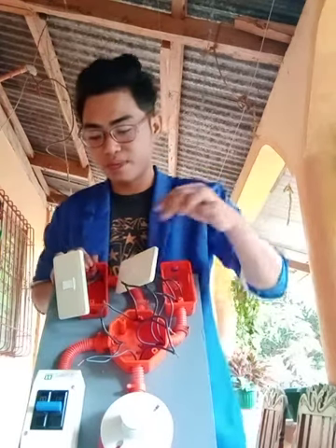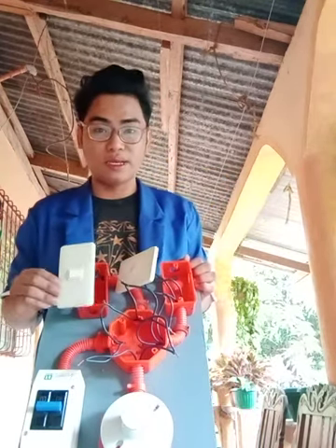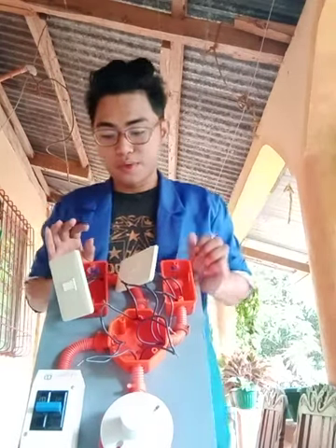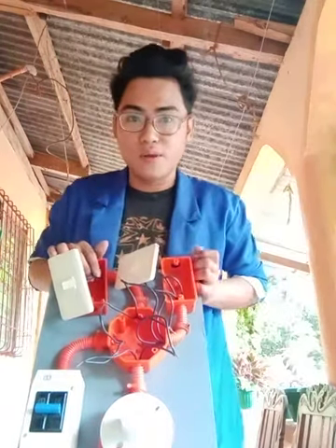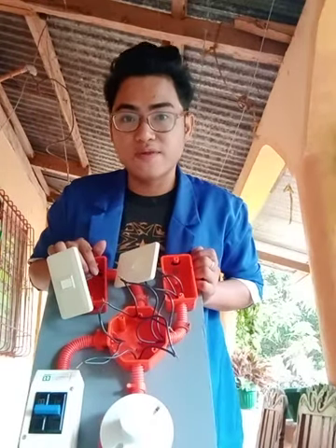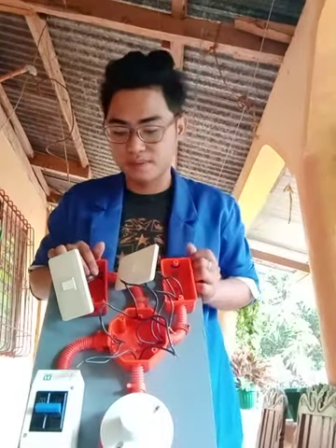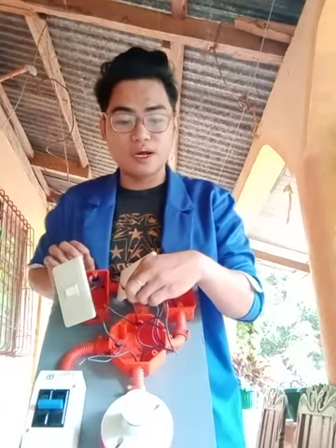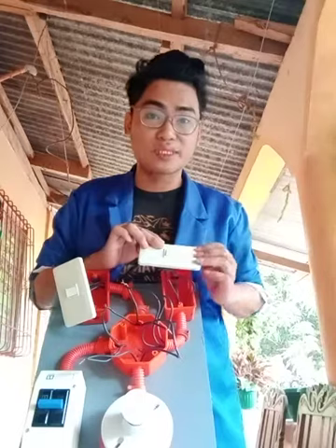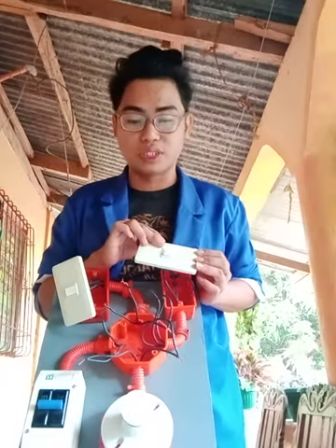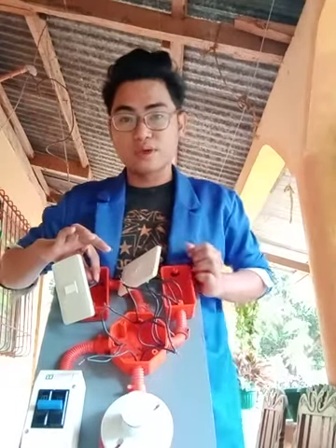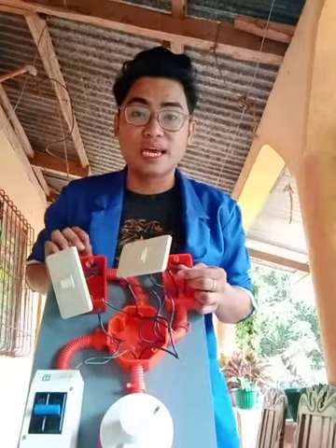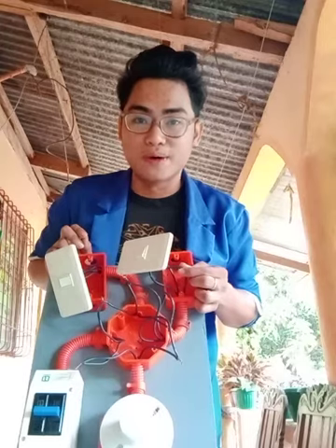After connecting the live wire from the circuit breaker to the common in the three-way wall switch, which is numbered as 0, we will now travel the wire using traveler 1 and traveler 3. We will first connect traveler 1 to traveler 1 of our second three-way wall switch. After, we will connect traveler 3 to traveler 3 of our second three-way wall switch.